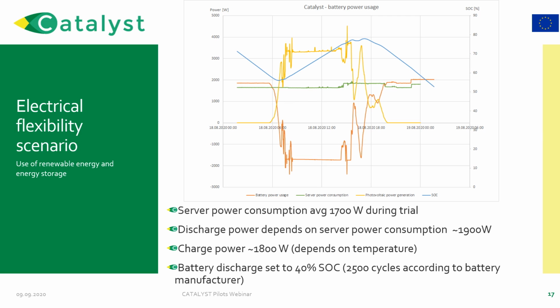You can see that when the photovoltaic system stops working, we discharge batteries, adjusting the discharge to avoid going below 40% state of charge, to avoid decreasing the lifetime of batteries. We do this using the power capping mechanism to lower the power so we don't discharge the battery. In this experiment we were able to reach 100% power supply from renewables. In the case where we have more servers connected, depending on the situation, it can be about 50%.